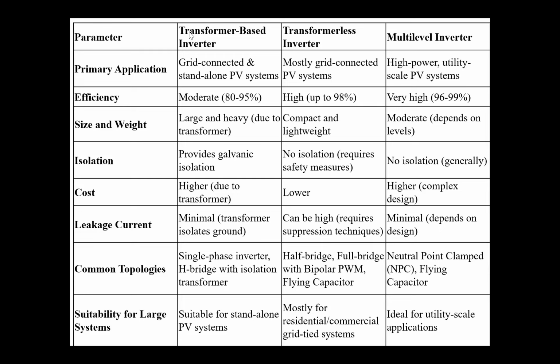Complex design. Leakage current. A very important point here is leakage current. It is minimal in the transformer-isolated ground case, and can be high in the transformerless inverter, which requires suppression techniques. It is minimal in multi-level inverters.